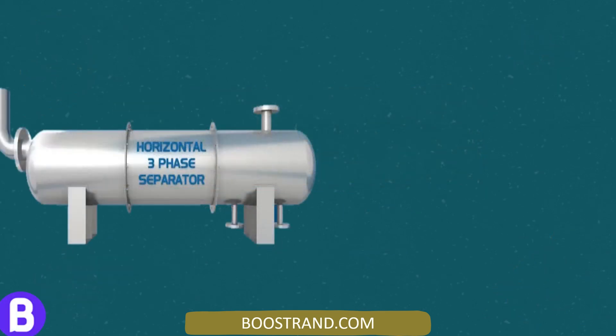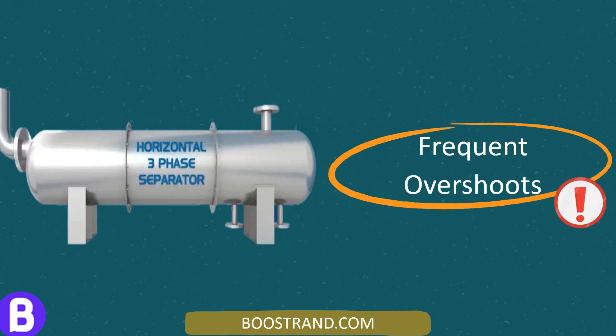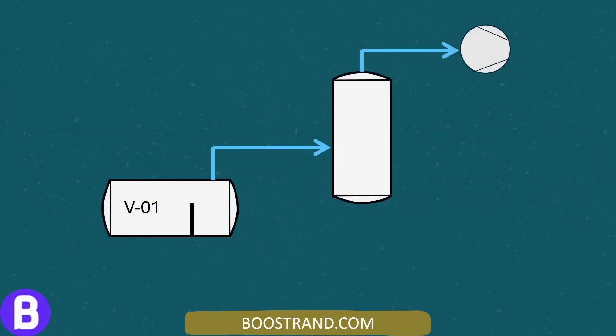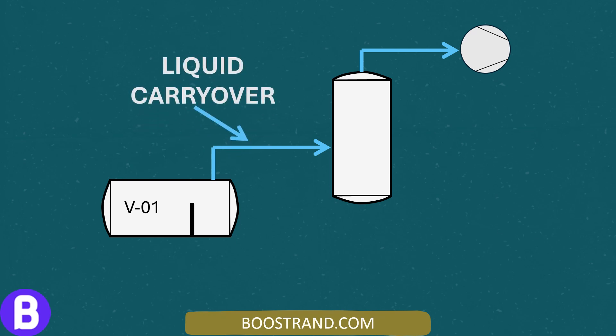In a three-phase separator at a crude oil production facility, operators started to notice that there were frequent overshoots in the level reading. In addition, as the gas is sent to a compression system, it was noticed that the downstream compressor suction scrubber started to receive more liquids than usual.